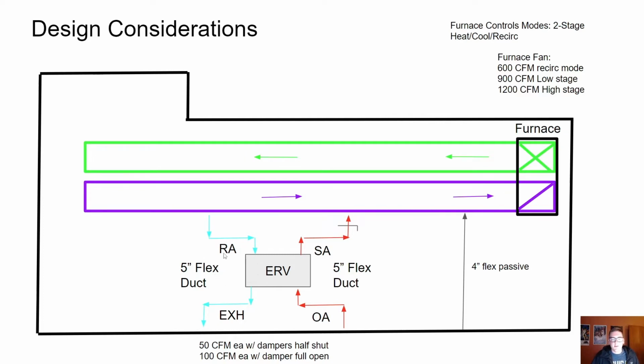So all my duct runs are 5-inch flex, and I also put a damper on this supply side. If I ever had to unplug the ERV and close that damper, then the furnace wouldn't be pulling unconditioned outdoor air through the ERV if the ERV was ever off and I had to make repairs or wanted to take it out or something like that.